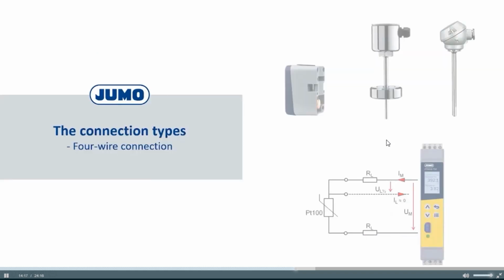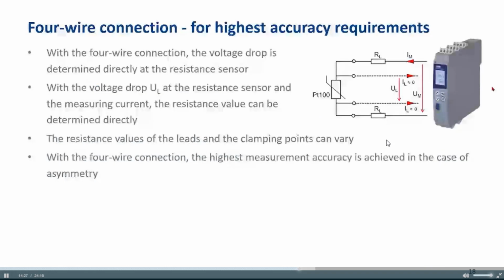So if you want to have the best accuracy, then you can work with a four-wire connection. Four-wire connection, you see it here. Then we say, let's give the current through this loop, and let's work with these two wires. With the help of these two wires, we measure the voltage drop on the Pt100. So we have no influence by the cable resistance. This is the best we can do.